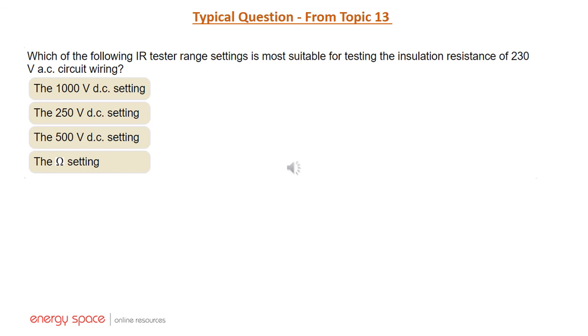In AS3000, as I've mentioned, we must use twice the applied voltage to test. So in this case, if the appliance is going to be used at 230 volts, the insulation tester must be set to at least twice the applied voltage, which would give you an answer of 500 volts. But that's covered in topic 13.